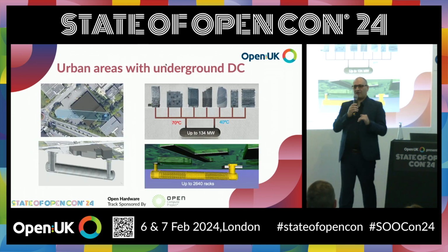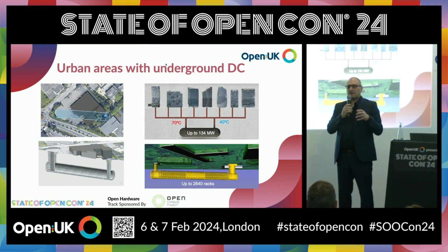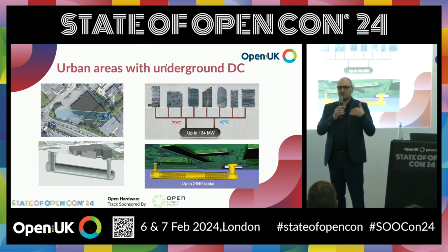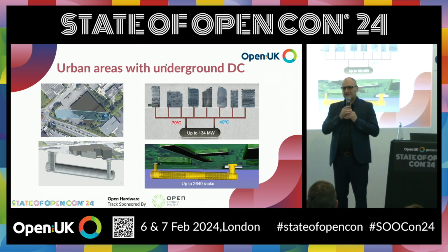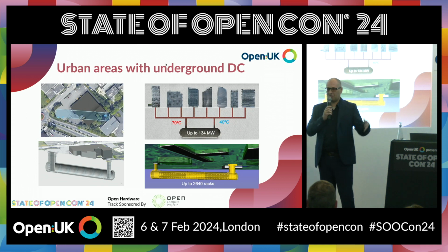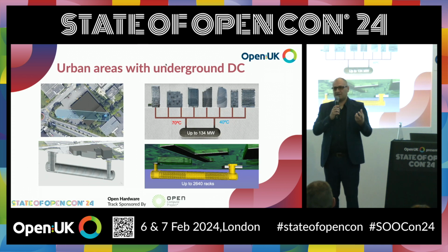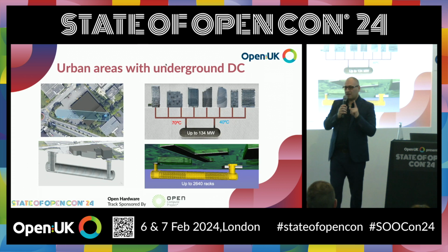Actually, when you go underground, you get a more stable and colder temperature. But when you have 100 megawatt heat rejection, and if you do not take that away, all your walls will be heated in 1-2 days. It will be hot. But if you don't have cooling for, let's say, 1 hour, 2 hours, 3 hours, these walls will accept that heat and allow you to keep working longer if you have any disruption in the cooling. But there are many other advantages.